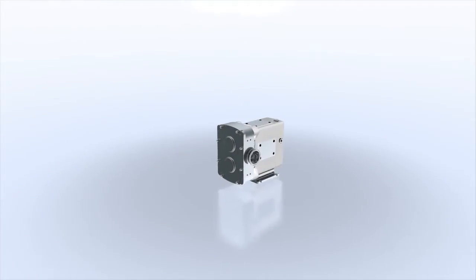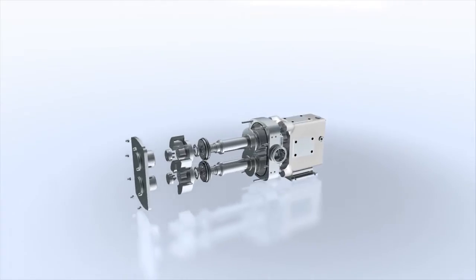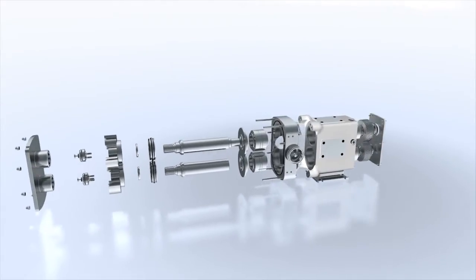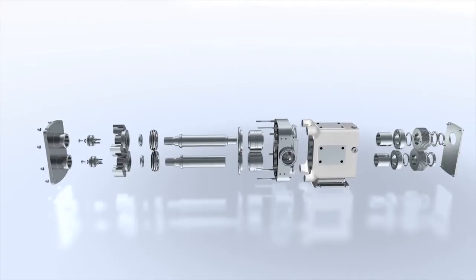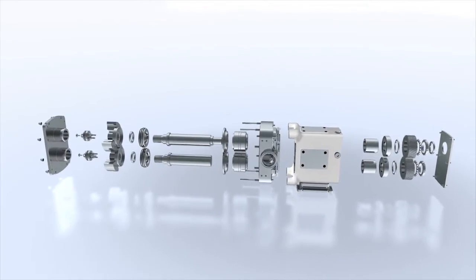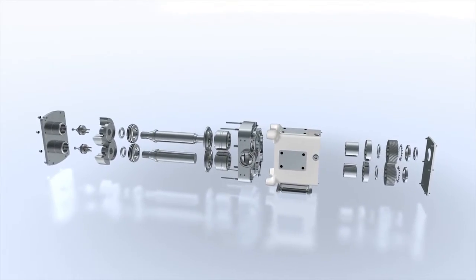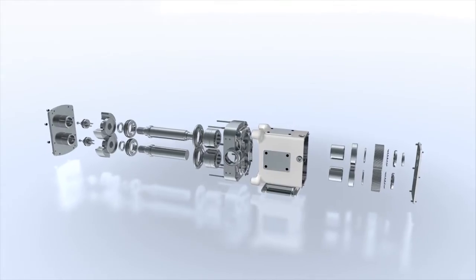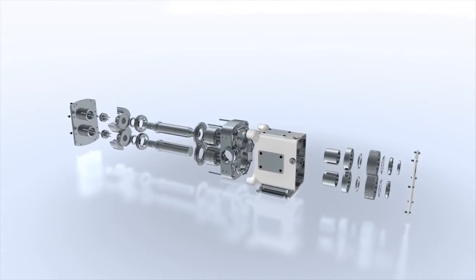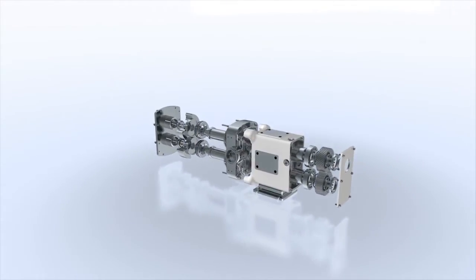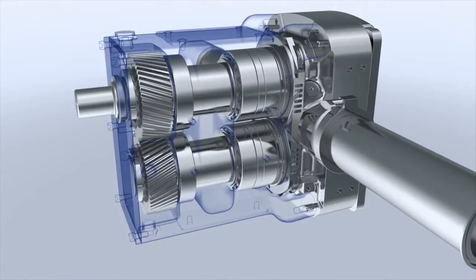Revolution is built with heavy duty shafts, bearings, and timing gears, reducing deflection and supporting discharge pressures up to 31 bar or 450 PSI. This design extends the life of seals, rotors, shafts, and bearings, further increasing your uptime.